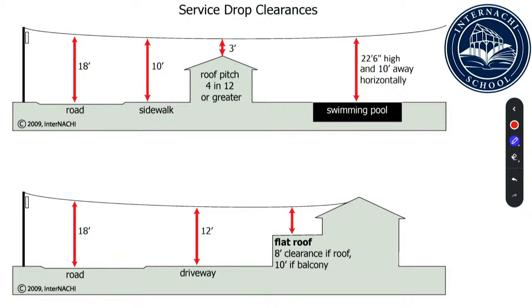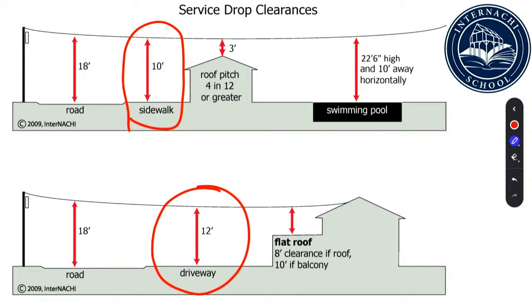Let's start with walk areas first. Whenever we walk — doesn't matter if it's a sidewalk, grass, a deck, or a flat roof with a walking surface — if there are power lines over an area where a person can walk, I need at least a 10-foot clearance. On a driveway for a house, that's got to have at least a 12-foot clearance. Going back to the 10-foot mark, we're not going to throw tape measures on there. You don't know if there's damaged insulation, and you'll be standing on the ground touching something — you just don't know. So it's going to be a rough estimate. A basketball hoop is 10 feet off the ground, so I like to use the rim of a basketball hoop as my comparison — a rough idea of how tall 10 feet is, so I can see if I have enough clearance.